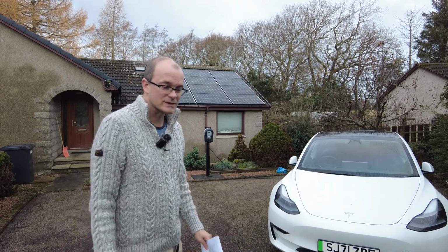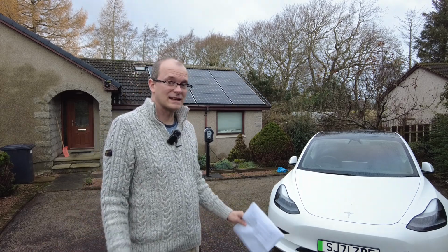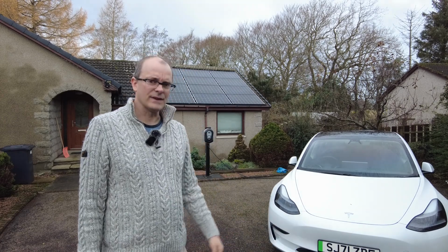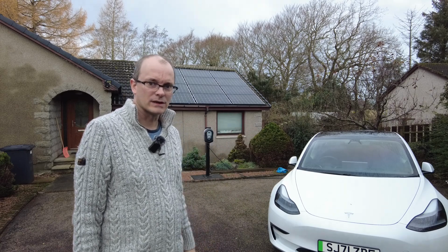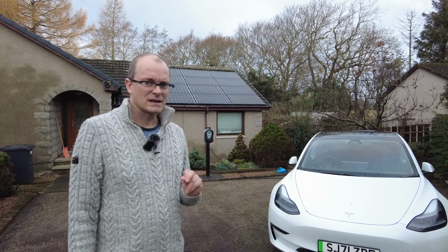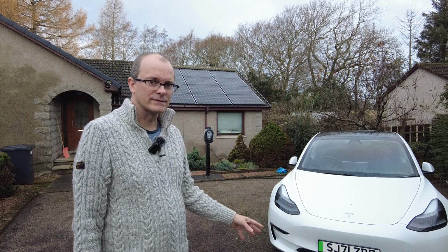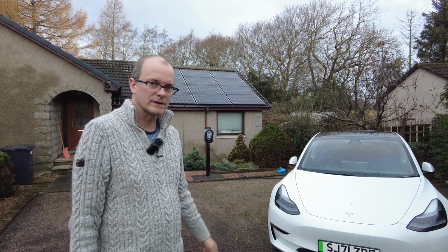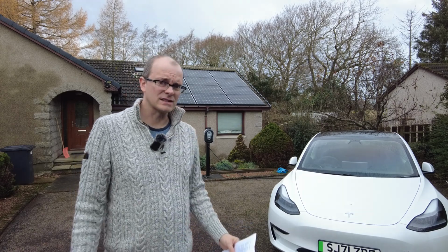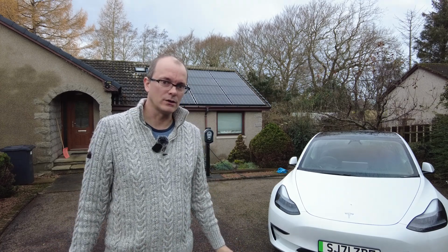But one of the things I will say is that the Solaredge system is absolutely fantastic in being able to report this defect in the first place. Now, if you had a standard solar panel string array without any Solaredge optimizers, you wouldn't discover this defect with one panel. You'd have to have quite a few panels defective before you'd actually discover that there was a problem with your solar panel system as a whole. So in that regard, the Solaredge system is excellent in being able to diagnose problems early on.